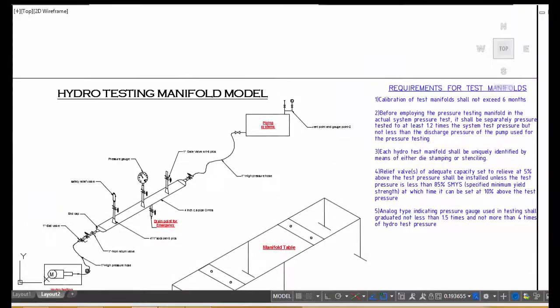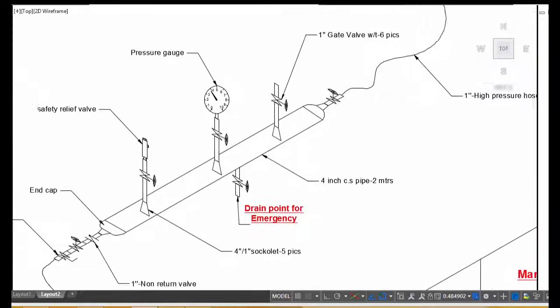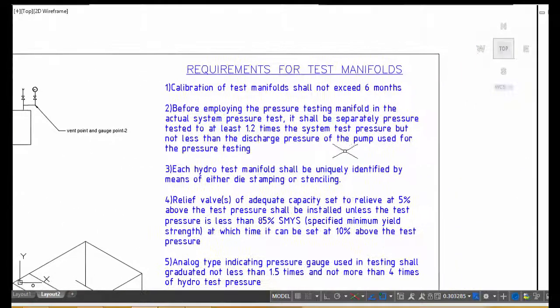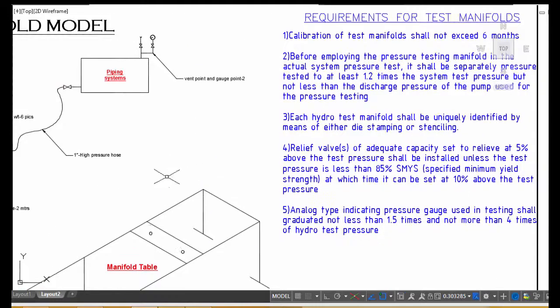At the time before using this manifold, you have to test it internally first. Here I mentioned calibration. Calibration of test manifold shall not exceed six months, and this manifold should be tested 1.25 times.